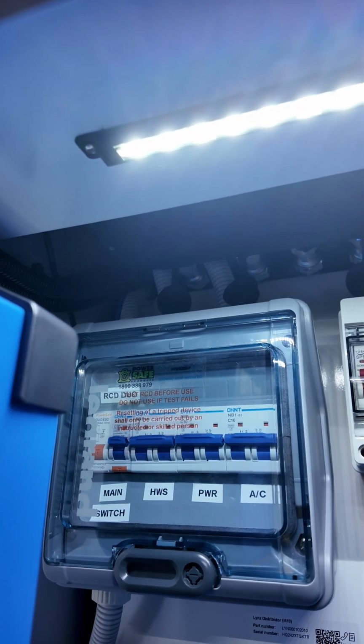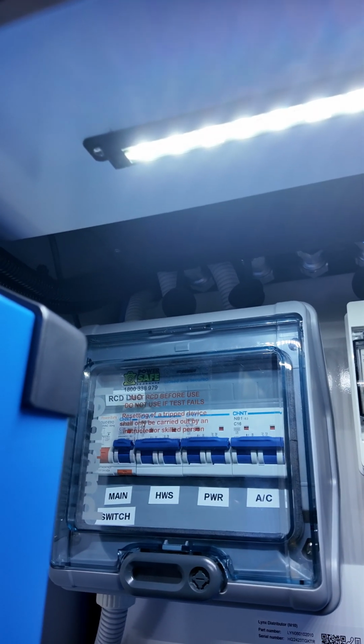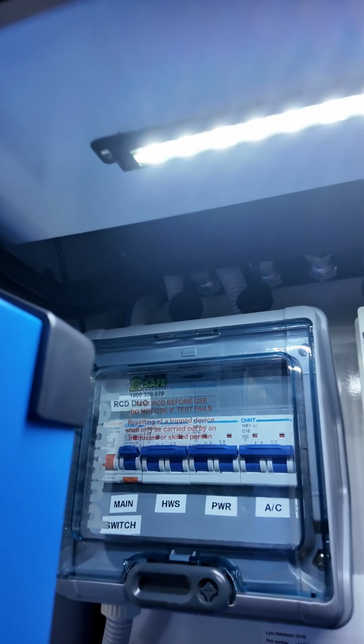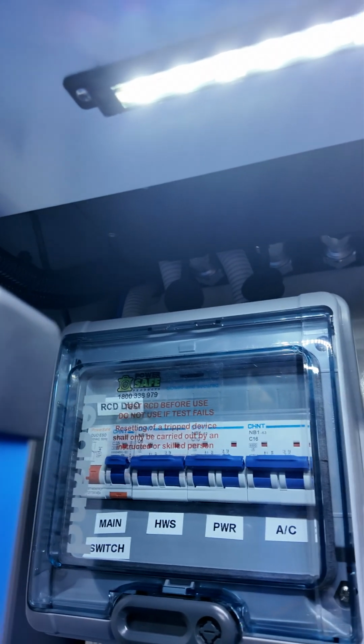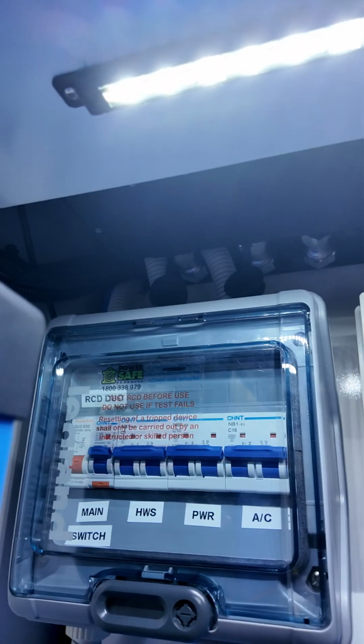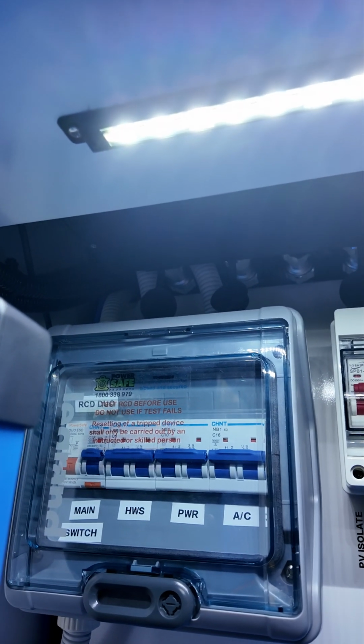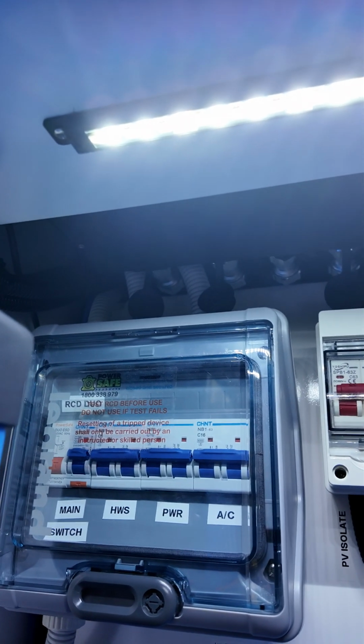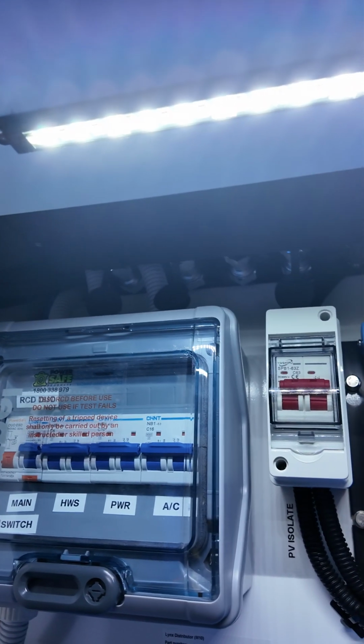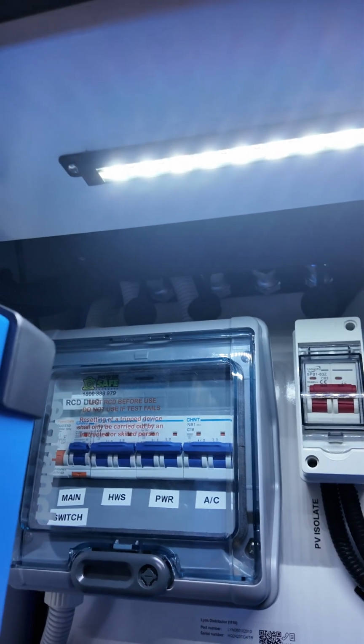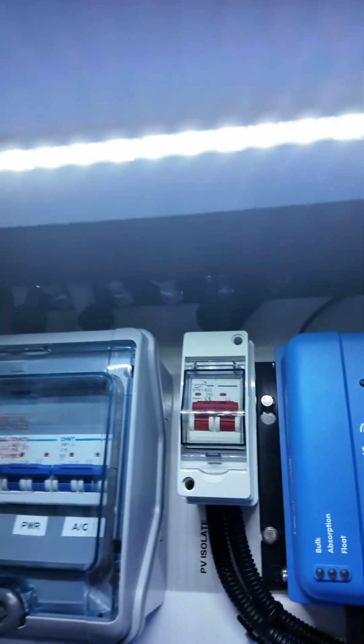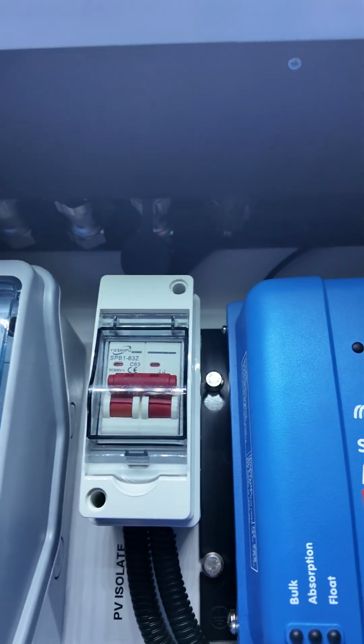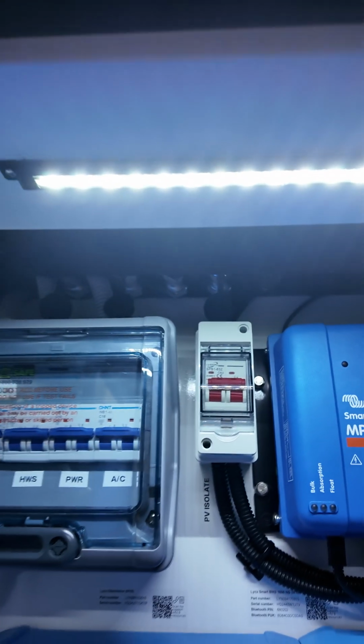So you've got your RCD, which is your safety breaker, and then it drops down into 3 smaller breakers for your hot water system, your general power, and your air conditioning. Everything's fused and isolated in the camper. You've also got your solar PV isolator up there. Everything's 2-pole, by the way.